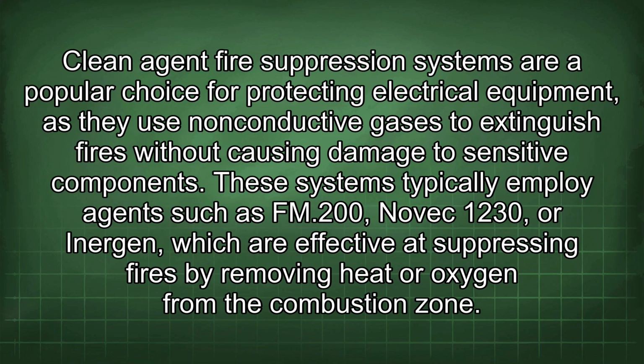Clean agent fire suppression systems are a popular choice for protecting electrical equipment, as they use non-conductive gases to extinguish fires without causing damage to sensitive components. These systems typically employ agents such as FM200, Novec 1230, or Inergen, which are effective at suppressing fires by removing heat or oxygen from the combustion zone.